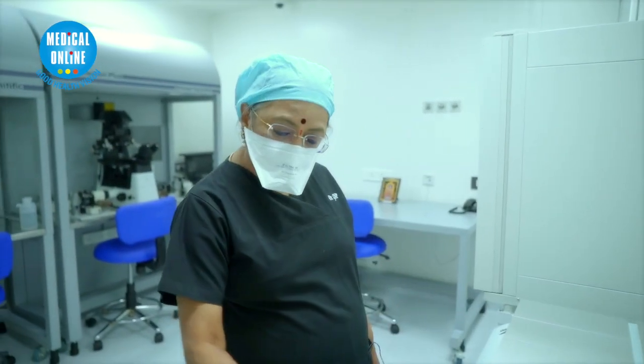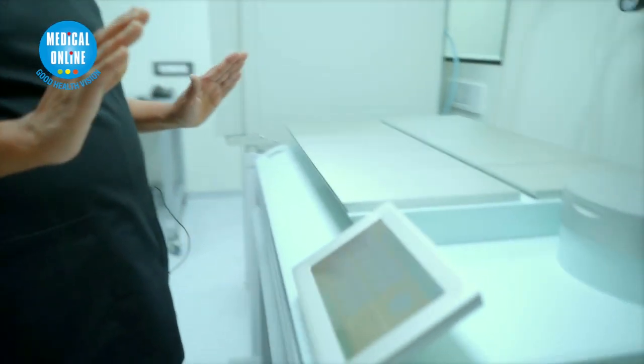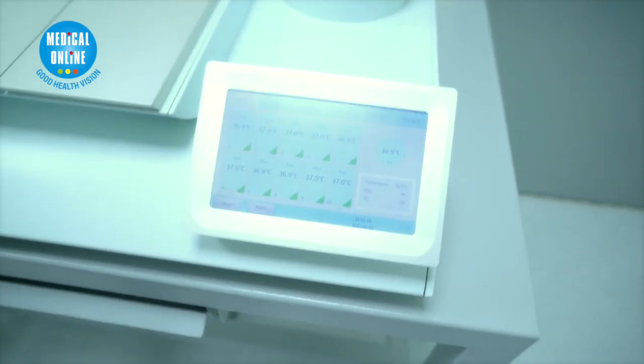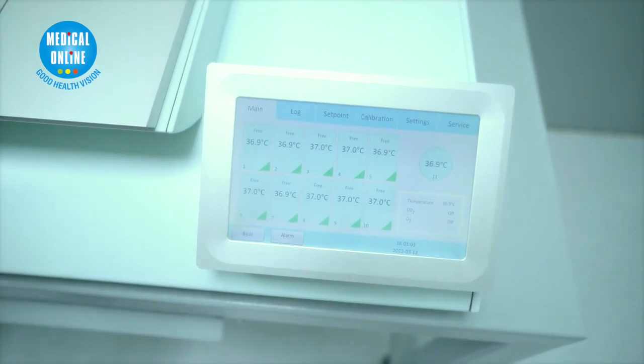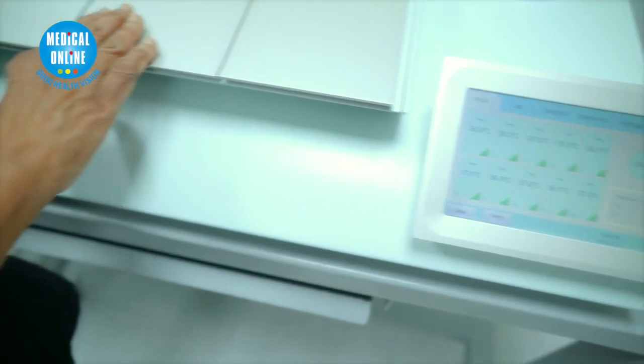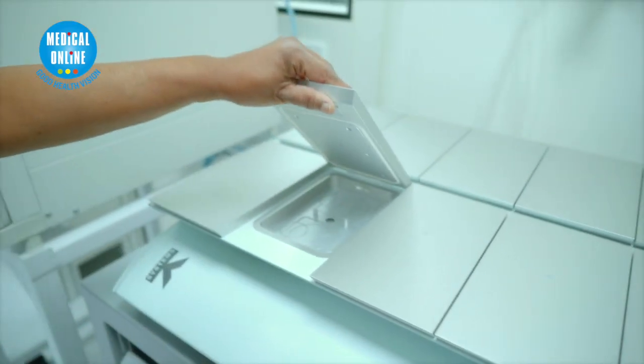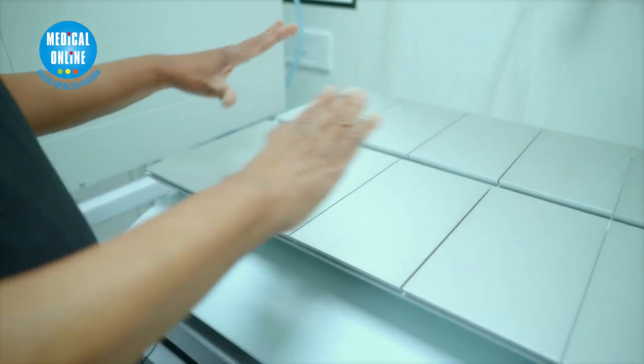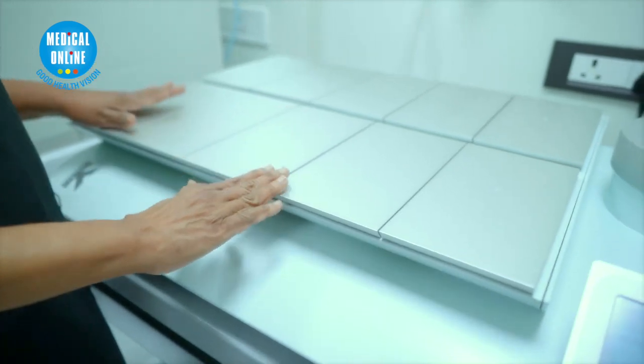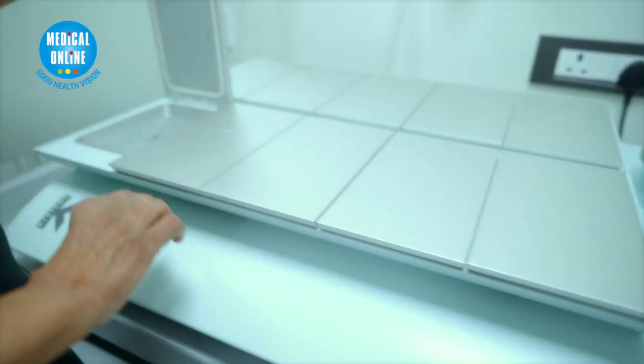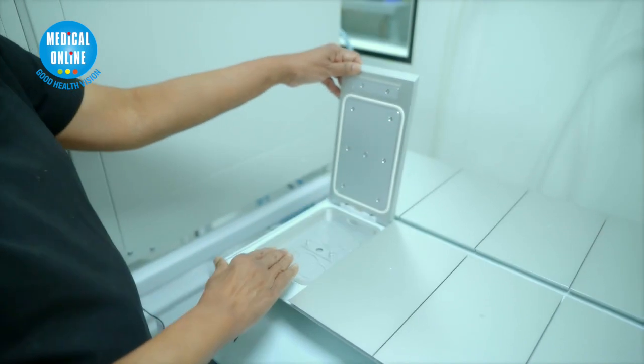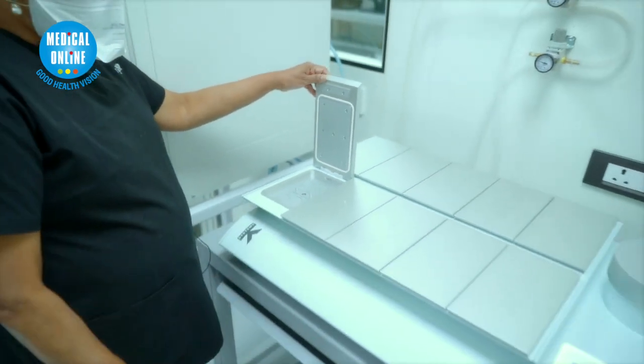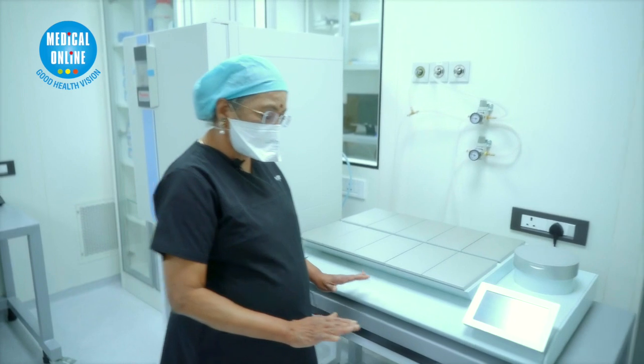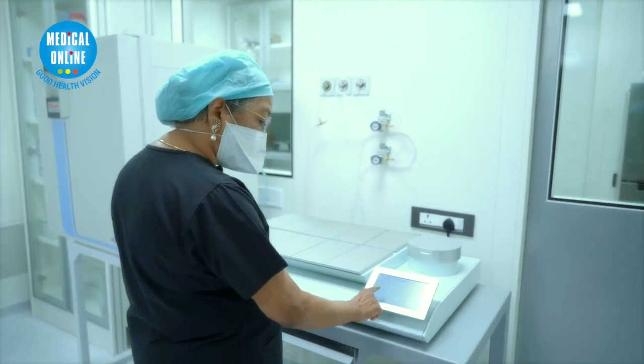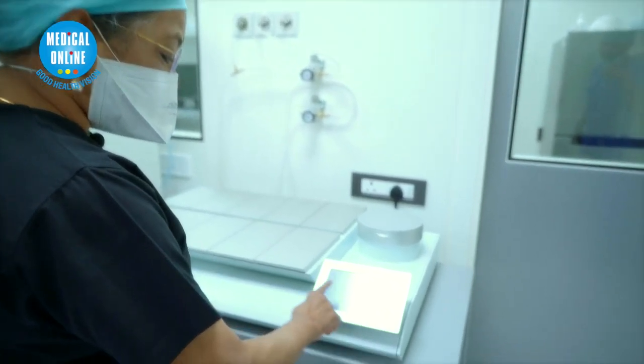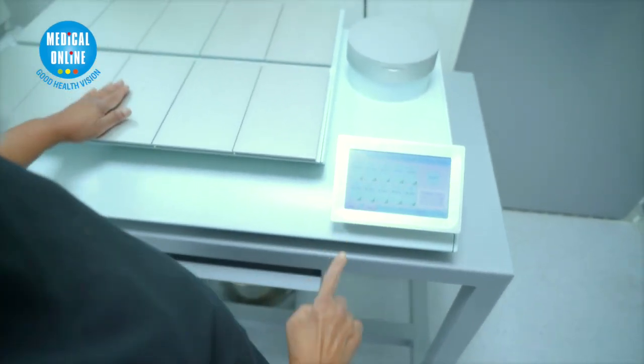Very important, this is one of the top-end incubators, and it has 10 chambers, and each chamber can accommodate 2 patients' embryos. So in toto, we can accommodate 20 patients' embryos in this incubator, and when you open it, make sure that only 2 patients' embryos are exposed and all the others are still kept in condition. You would note that all these settings are for each system.